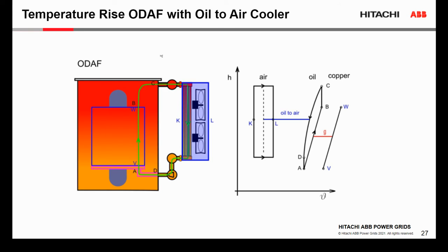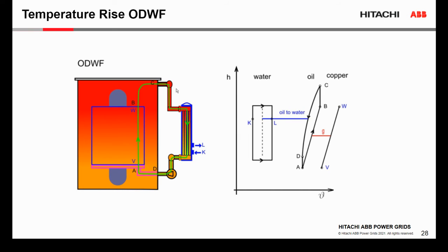And the same solution we can have with oil-to-air coolers, but the difference is that we don't have ON stage. So basically, when the transformer is loaded, the cooling system must be on and running. And this is the solution with oil directed and water coolers connected to the transformer. So this is a very common solution in hydroelectric plants, because we have easy access to water.